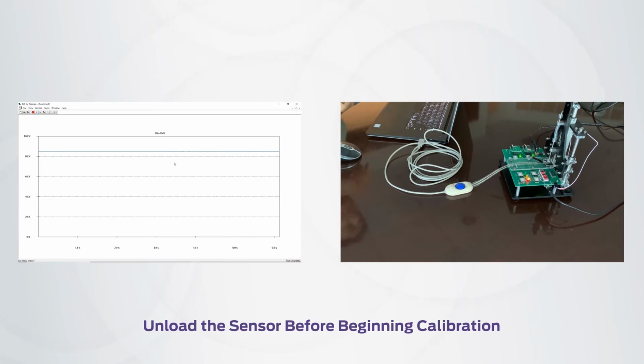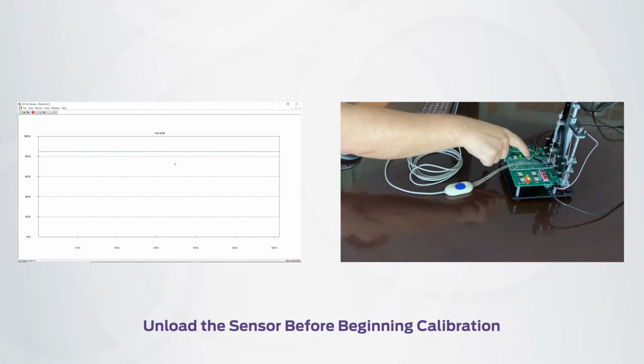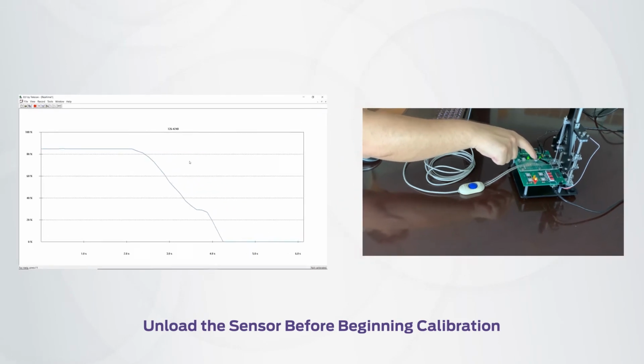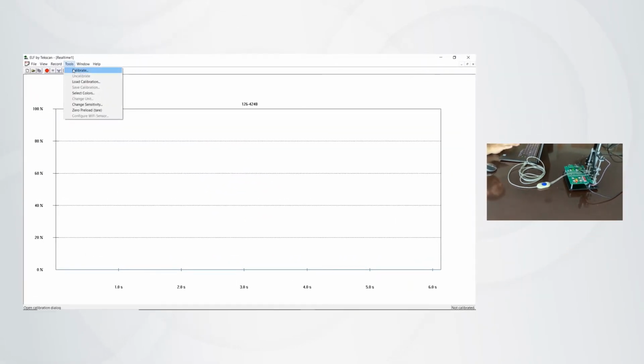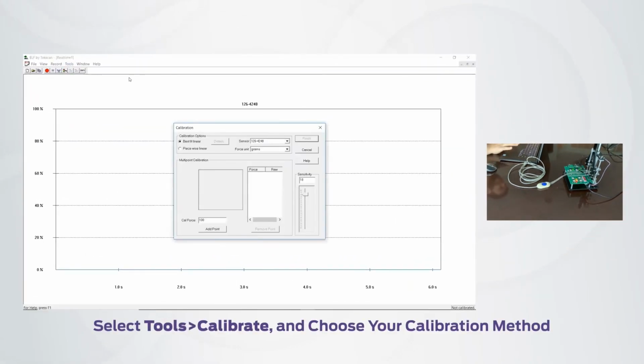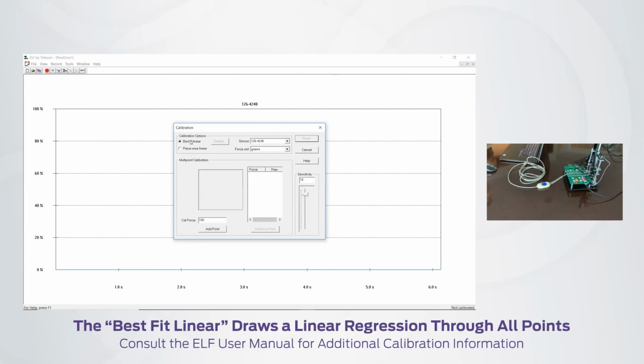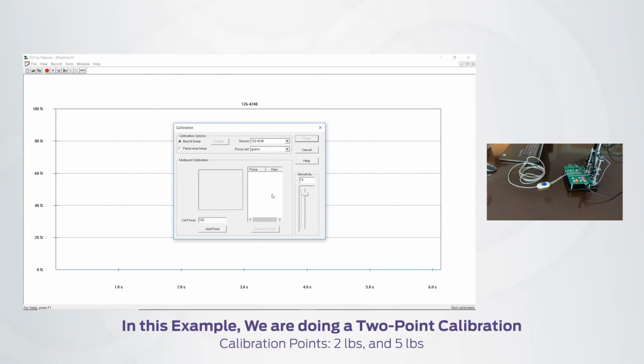So to calibrate, we'll first unload the sensor. So we'll go into Tools, Calibrate. In this case, I'm going to opt for the best fit linear. So the best fit linear will essentially draw a linear regression through all of your calibration points. So I'll be doing a 2-point calibration. One point will be at about 2 pounds, and then the second point will be at 5 pounds.